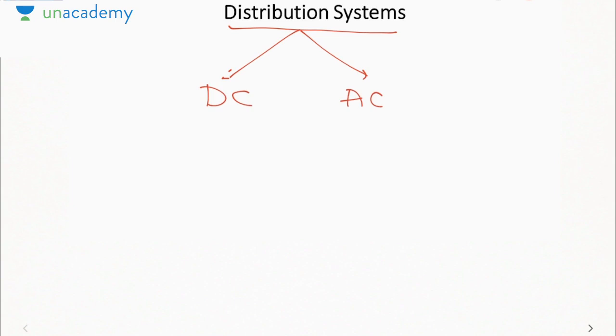As we all know, in our homes whatever power we use is in the form of AC. So what is the basic purpose of a DC distribution? Actually, DC distribution acts as a backup in the generating stations and the substations. Suppose somehow the power goes off, then all the equipment operating in such a substation must be protected. They must have a reliable power supply so that they do not turn off instantly, otherwise they will experience a power surge or a sudden power down. That is not desirable, so we maintain a backup in the form of DC distribution.